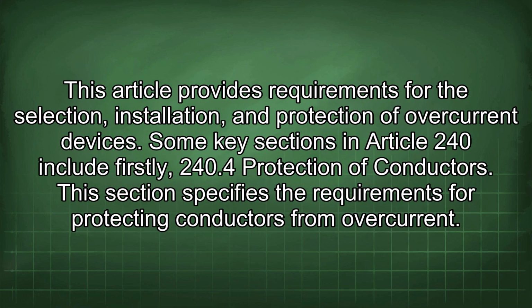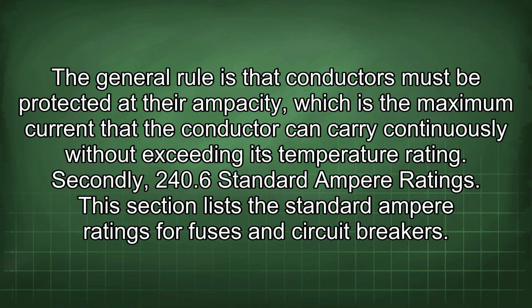This article provides requirements for the selection, installation, and protection of overcurrent devices. Some key sections in Article 240 include, firstly, 240.4 Protection of conductors. This section specifies the requirements for protecting conductors from overcurrent. The general rule is that conductors must be protected at their ampacity, which is the maximum current that the conductor can carry continuously without exceeding its temperature rating.